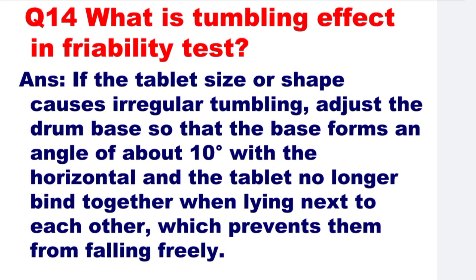Next: What is the tumbling effect in friability test? If the tablet size or shape causes irregular tumbling, adjust the drum base so that the base forms an angle of about 10 degrees with the horizontal, so that the tablets no longer bind together when lying next to each other, which prevents them from falling freely.